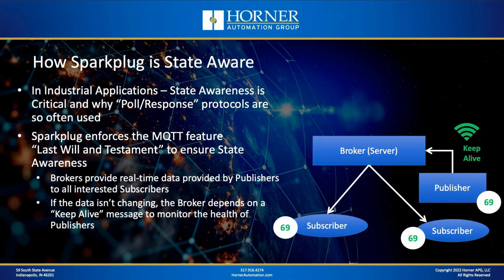So even if my data isn't changing, I'm going to send a simple 2-byte message periodically that says, yep, I'm still here, I'm still alive, everything is good. And then as subscribers are looking at my data through the broker, of course, they can also be confident that the data they have is the latest copy and it's up to date.